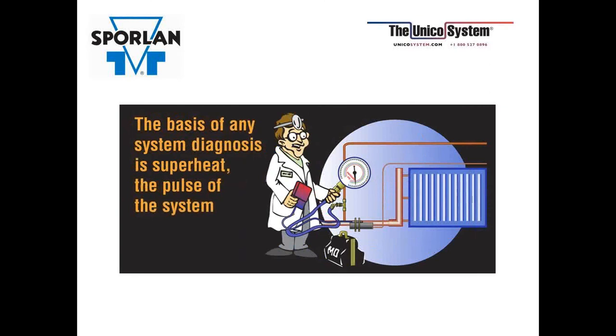The basis of any system diagnosis is superheat. It's the pulse of the system. And the very definition of superheat reminds you that you have to take a good suction pressure reading at the bulb as well as the actual temperature. And without a superheat value, any diagnosis that you come up with is haphazard at best.